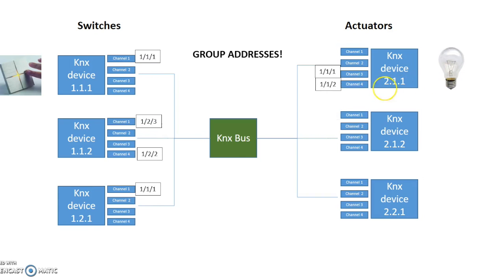In this case there's just one actuator which turns on this light. The devices are linked together by things called group addresses, which are different from the individual device addresses. These are the linking addresses which will link, say, channel 1 of device 1.1.1 with channel 3 on another device. Each channel can be given one or a series of different group addresses, so that channels are linked together through these group addresses.